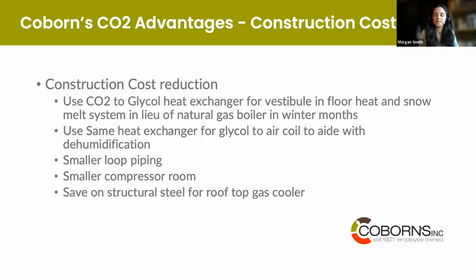Chris, what about you? Some of the advantages that stood out to you? So some of the advantages that we've seen on the construction cost reduction. We've used the CO2 to glycol heat exchangers, and we use the glycol to heat the vestibule in-floor heat for snow melt in lieu of a natural gas boiler in winter months. So we're able to eliminate the cost of that boiler altogether. We use the same heat exchanger for glycol to an air coil to aid with dehumidification in the summer.